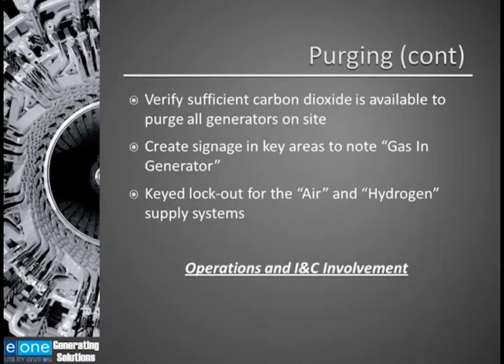I like the idea of creating signage to put in key areas to note what gas is in the generator. Obviously, during normal operation you have hydrogen in the generator, but during the purging process, it's possible that you have either CO2 or air in the generator. So this signage can be placed at the gas manifold, at the hydrogen purity analyzer, and also up in the control room.